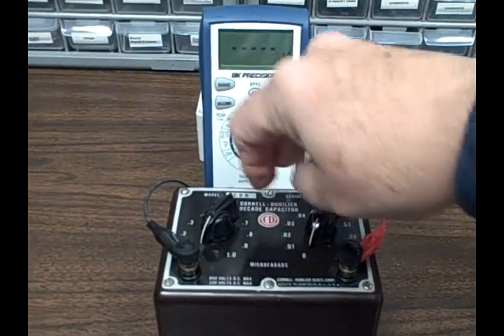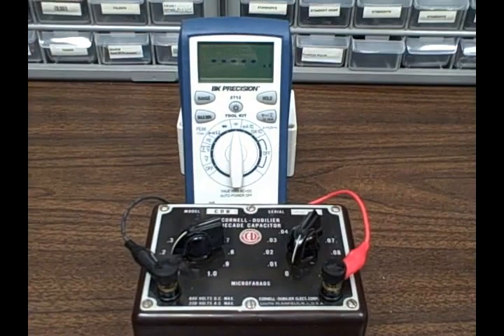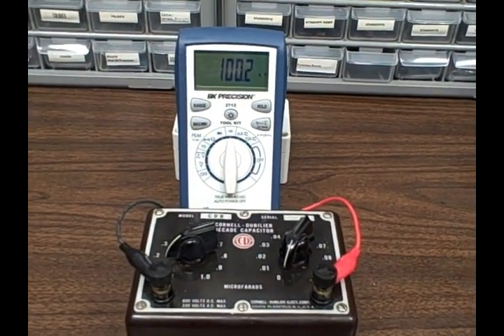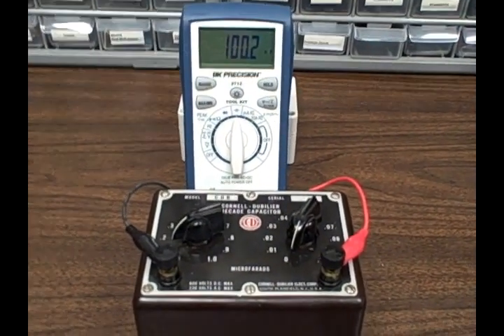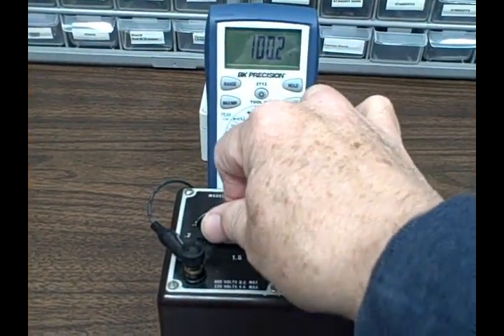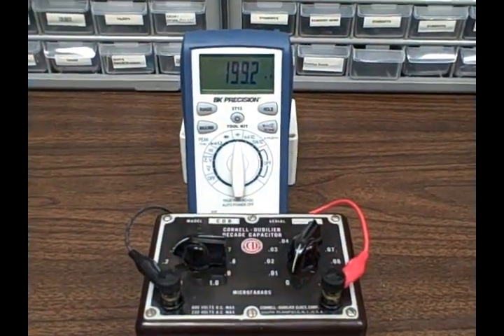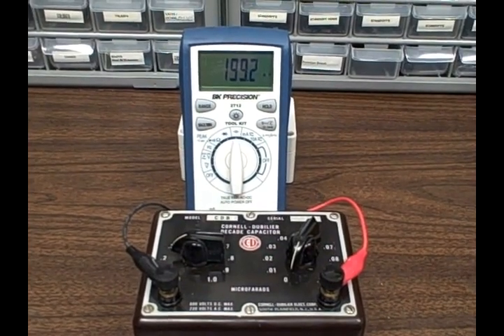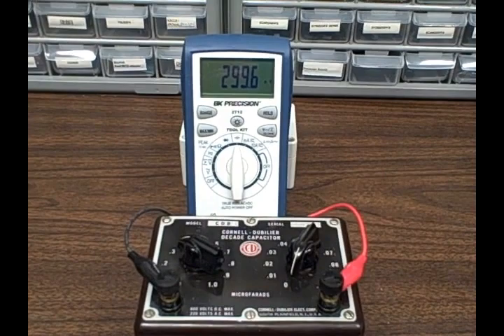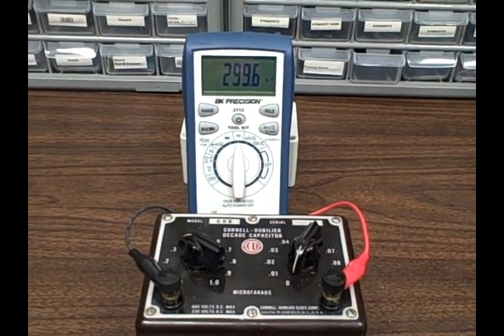All right, let's go back down to zero. We're going to take a look at the most significant figure. This would be 0.1 microfarads, the first decade. I'm getting 100.2 nanofarads. 0.2 microfarads, I'm getting 199.2. 0.3 microfarads, 299.6.